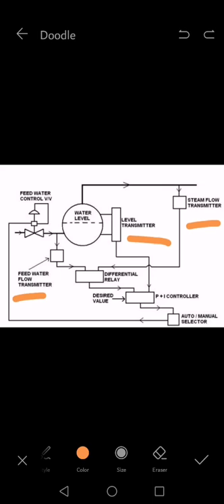The output signal from the P+I controller will go to the feed water control valve, telling it that the boiler needs to maintain this water level and water should flow at this many meter cube per hour so that we can cope up with the steam demand. The signal goes to the feed water control valve and tells the valve to open a little.